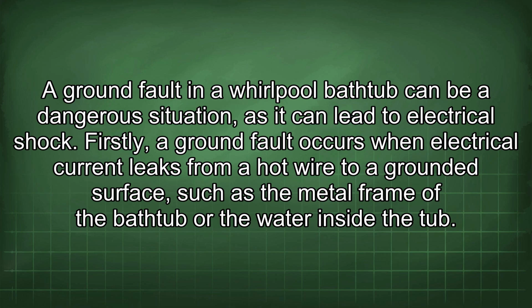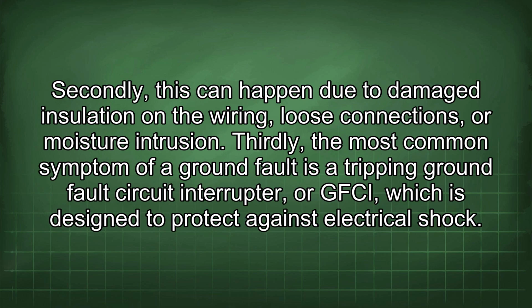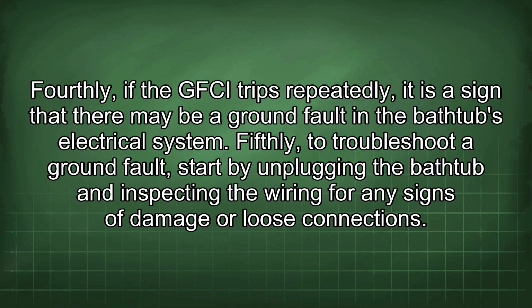A ground fault in a whirlpool bathtub can be a dangerous situation as it can lead to electrical shock. Firstly, a ground fault occurs when electrical current leaks from a hot wire to a grounded surface, such as the metal frame of the bathtub or the water inside the tub. Secondly, this can happen due to damaged insulation on the wiring, loose connections, or moisture intrusion. Thirdly, the most common symptom of a ground fault is a tripping ground fault circuit interrupter, or GFCI, which is designed to protect against electrical shock.